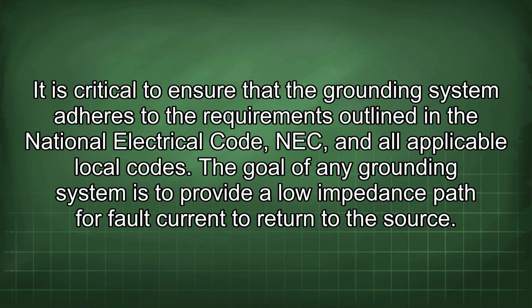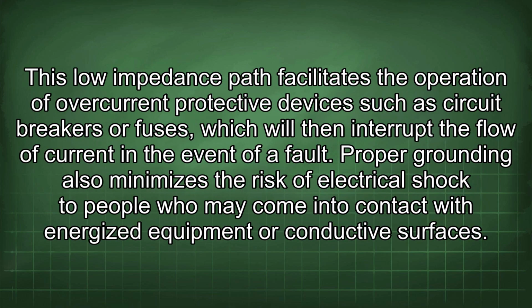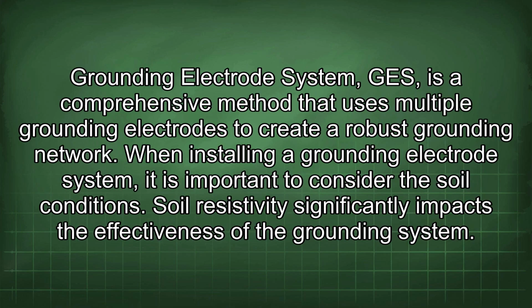The goal of any grounding system is to provide a low impedance path for fault current to return to the source. This low impedance path facilitates the operation of overcurrent protective devices such as circuit breakers or fuses, which will then interrupt the flow of current in the event of a fault. Proper grounding also minimizes the risk of electrical shock to people who may come into contact with energized equipment or conductive surfaces.